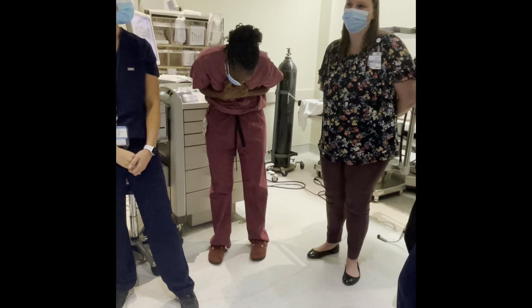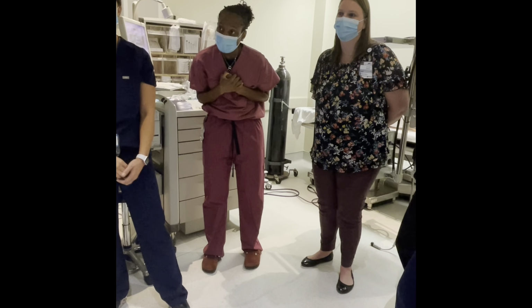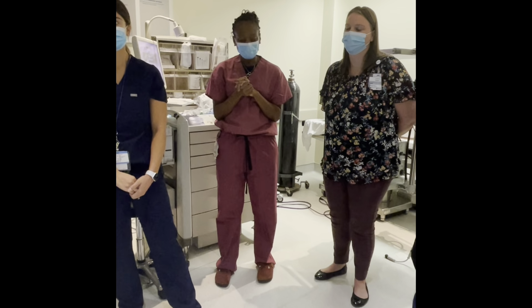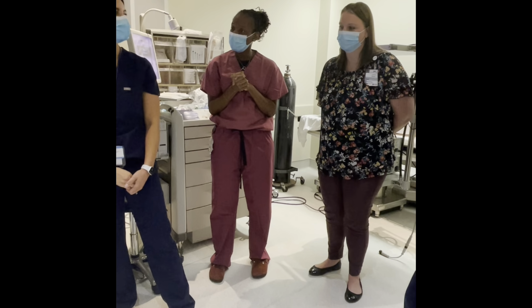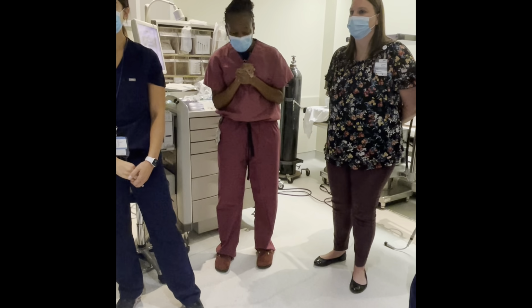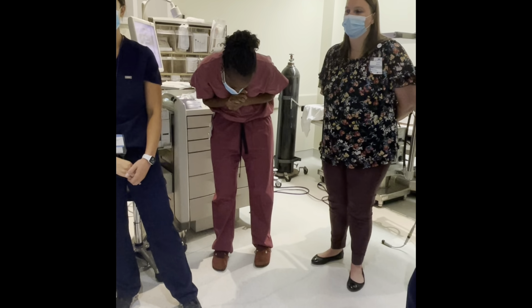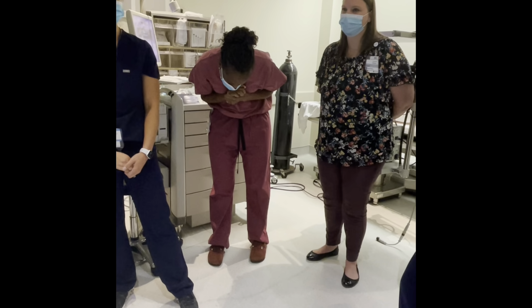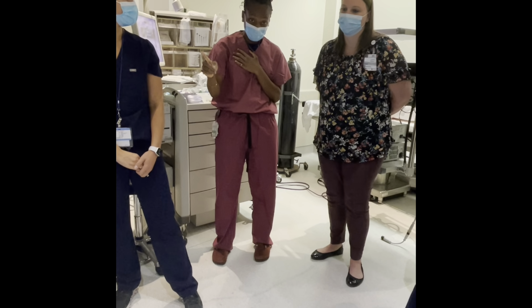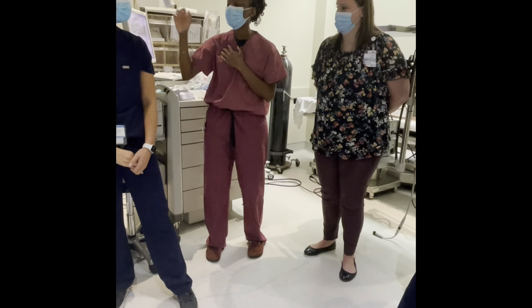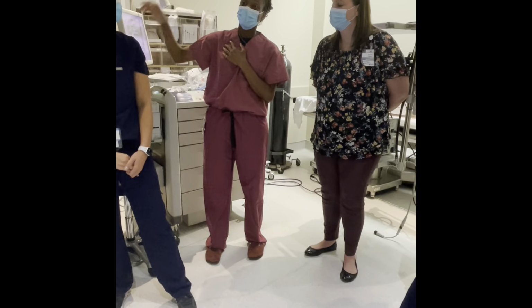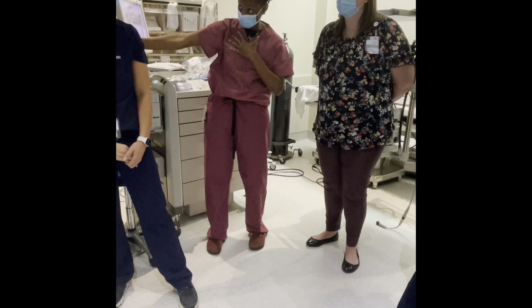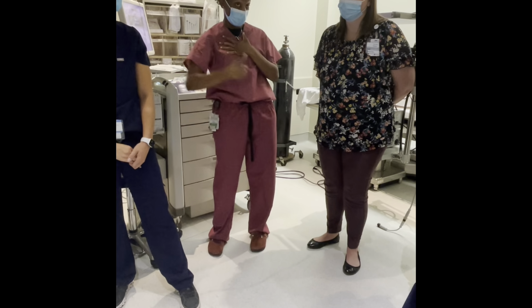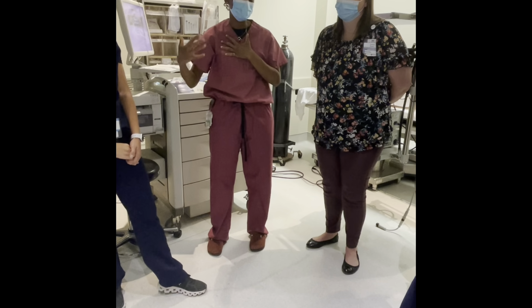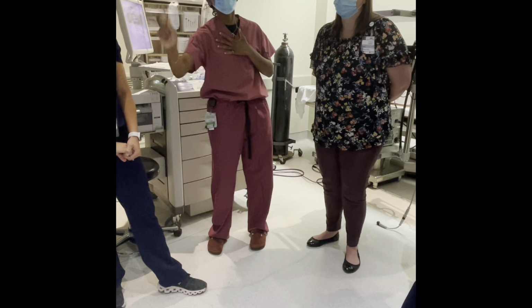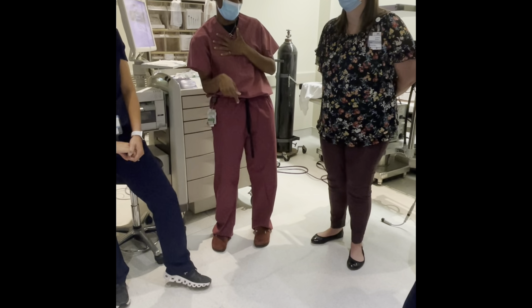Because the pressure in the pipeline is higher than the pressure in the cylinders after it passes through the pressure regulator. So it's going to be like 45 in the pipeline and 15 in the cylinder. And that's so the gas, if you accidentally forget to turn off your cylinder, the gas will not leak out of the cylinder. It will not unless something happens, right? If you accidentally leave it open, typically the machine will still pull from the pipeline because the pipeline is, like she said, higher than the cylinder after it comes to the regulator, right? Unless something happens. What will happen though? An alarm will happen, but something happens before the alarm happens.